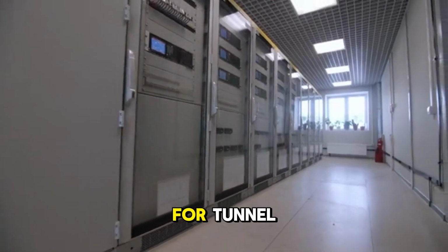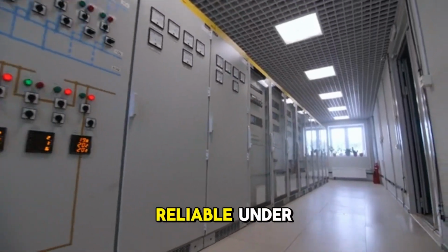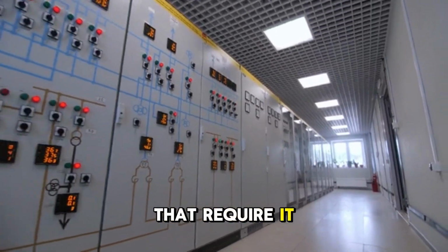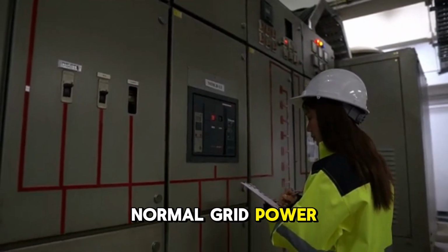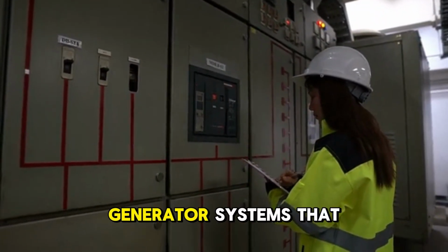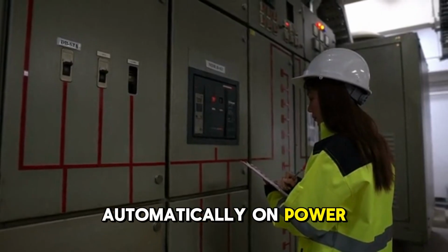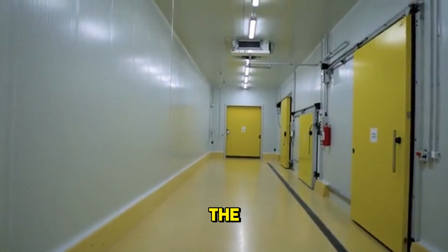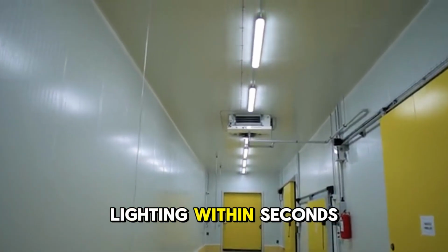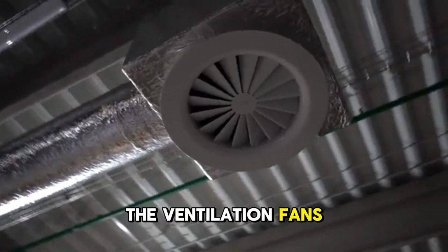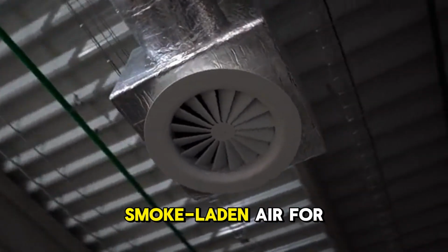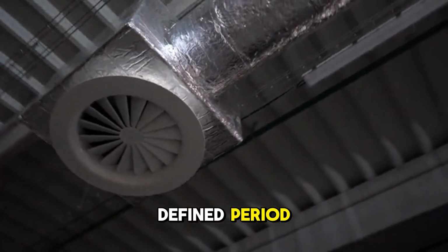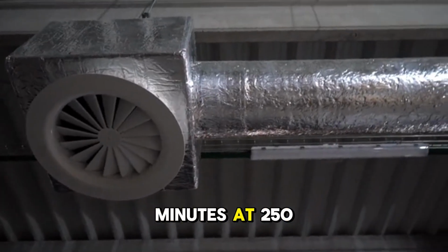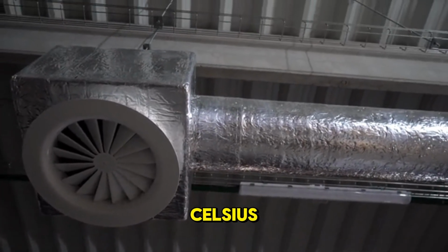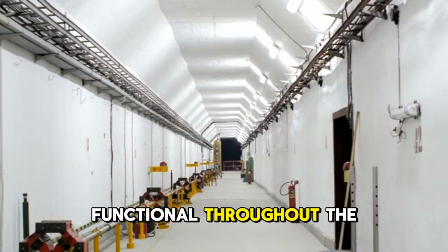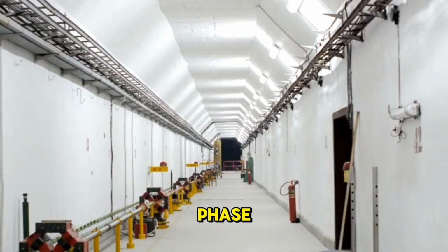The power supply for tunnel ventilation must be reliable under the same emergency conditions that require it most. Normal grid power is supplemented by emergency generator systems that start automatically on power failure and can supply the ventilation fans and emergency lighting within seconds. The ventilation fans are designed to operate in high-temperature smoke-laden air for a defined period, typically 120 minutes at 250 degrees Celsius, to ensure they remain functional throughout the evacuation and firefighting phase.